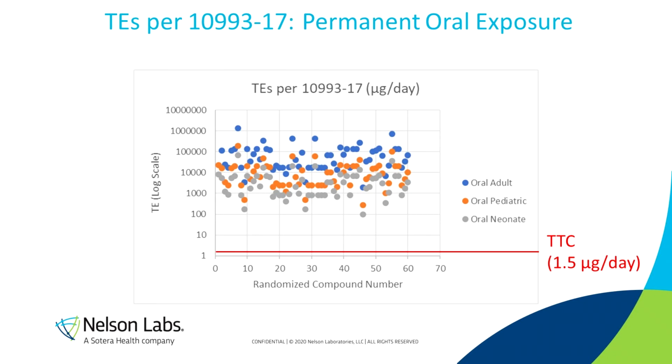So all of the NOEL data that I found, this experimental tox data, was in the form of oral exposures to rats. So the most clear connection, if we were going to apply that data to an actual use scenario, would be if the use scenario also was like an oral exposure. And a case where that happens very commonly is in gas pathway medical devices where water can condense inside the gas path, and it's possible that the user of the device might swallow some of that condensed water. And so that was what I was kind of imagining here.